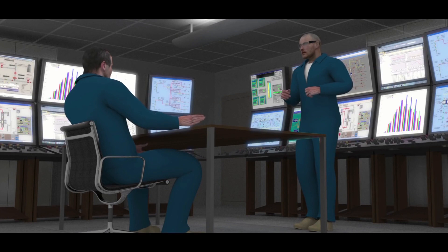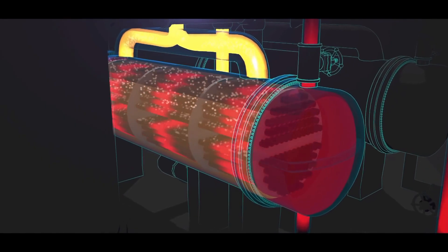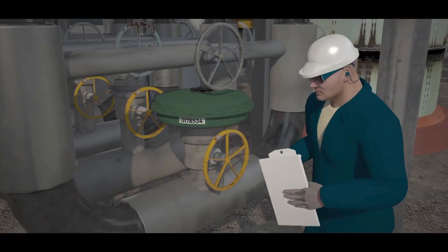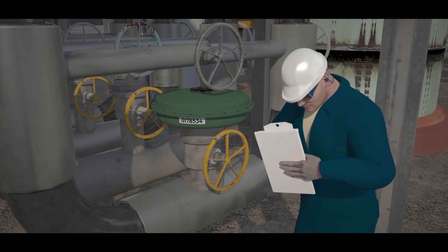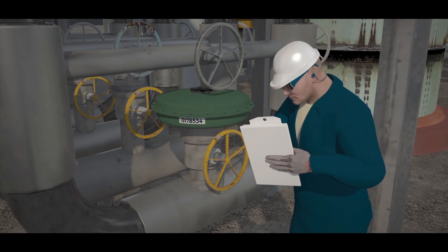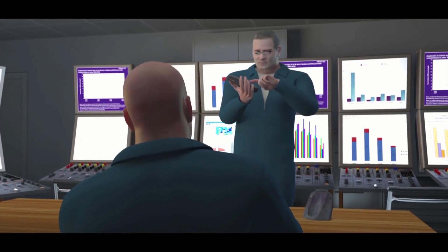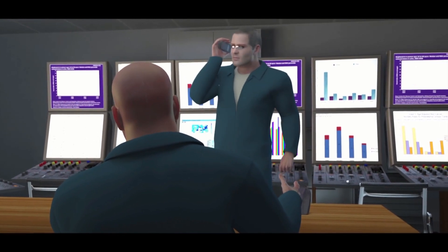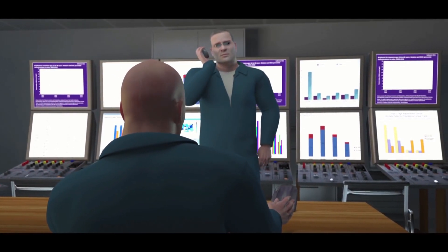On June 13, 2013, during a daily meeting with operations and maintenance personnel, the Williams plant manager noticed that the water flow rate through the operating reboiler had dropped gradually over the past day. The operations supervisor informed the group he would try to identify the problem. He went into the plant to evaluate the water flow rates. The operations supervisor informed several personnel that fouling within the operating reboiler could be the problem, and they might need to switch the reboilers. He attempted to meet with his manager to get the necessary maintenance and operations personnel involved, but his manager was not available.